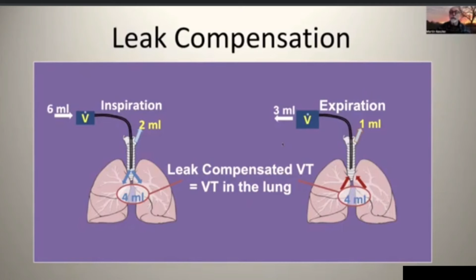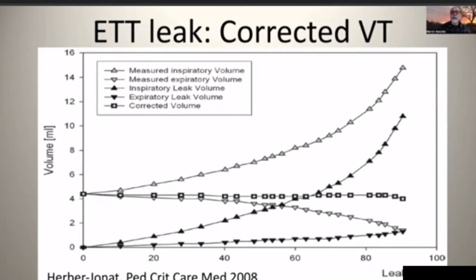And you can see that here on an older study that basically tested this hypothesis. So we have here on the horizontal axis progressively larger leak going up to 60–80% and beyond. And the measured inspiratory tidal volume, of course, progressively deviates from the actual tidal volume of 4 ml, going way up when you exceed 80%. The exhaled tidal volume deviates less. In this study, they used rather low end expiratory pressure. The higher the PEEP, the more leak you're going to see during the expiratory phase. What you can see here is the corrected or calculated tidal volume, which remains remarkably stable despite leak between 60 and 80%. So this works really well, and there's really no more of a concern as long as you're using the leak compensation.